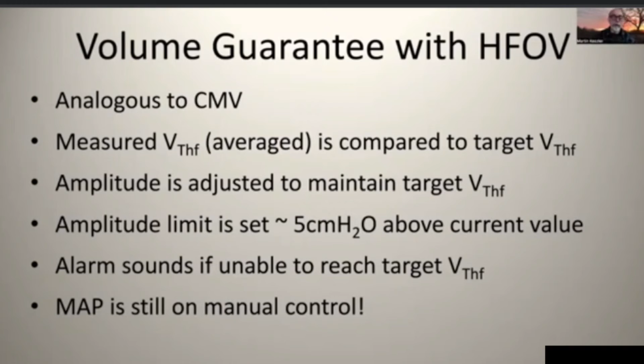And just like with conventional, there's an alarm. And you have to remember that your mean airway pressure, your other control with high frequency, is still on manual control. But amplitude, which controls CO2, is automated. All of you who use oscillatory ventilation know that tidal volume delivery is frequency dependent. And at lower frequencies, for any amplitude setting, you get a bigger tidal volume than at higher frequencies.